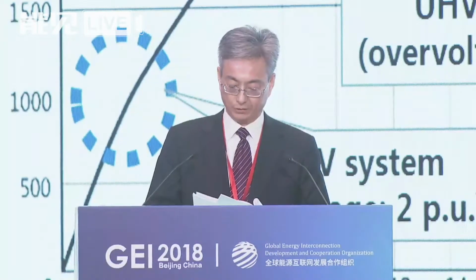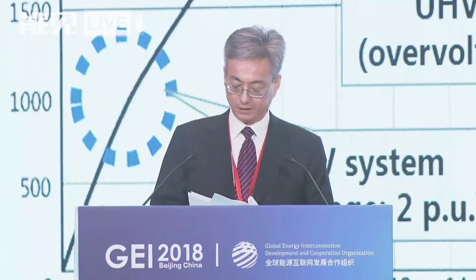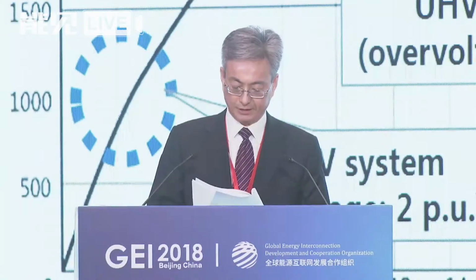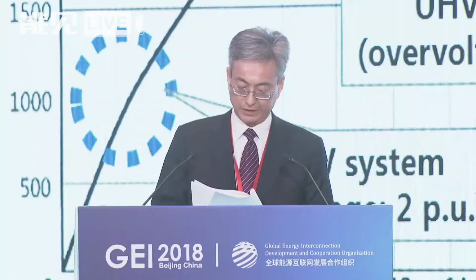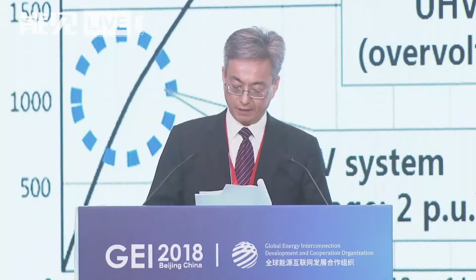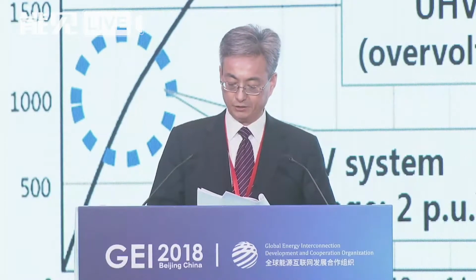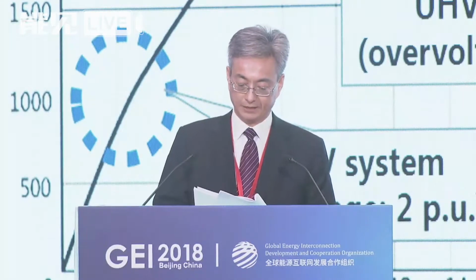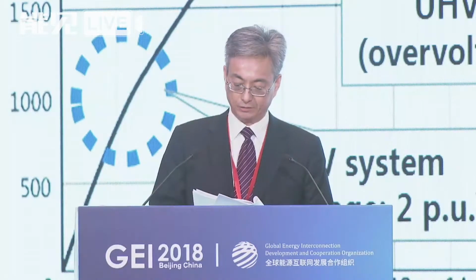For 500 kV systems, the overvoltage is usually 2 pu and is still in the unsaturation range. With large capacity, long distance, and complex electromagnetic environment, overvoltage control is more challenging for UHV systems. It will enter the saturation range even for overvoltage control to 2.0 pu, and the cost is unaffordable, with quite demanding requirements for equipment, so great efforts must be made on overvoltage suppression.